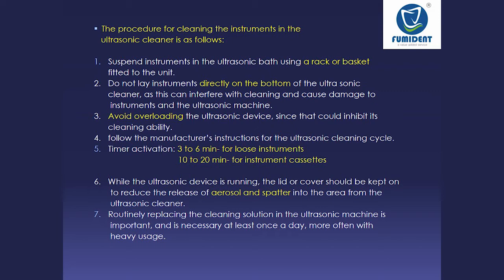remove it from the instrument. So according to the manufacturer guideline, there must be a dedicated time required to clean this instrument. For example, 3 to 6 minutes required for loose instruments and 10 to 20 minutes are required for instrument cassettes. So again, a few things that you have to take care of during cleaning of the instrument in the ultrasonic cleaner.